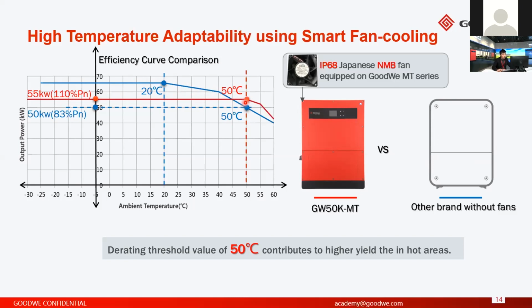But only if the temperature is more than 50 degrees, the inverter starts to decrease the AC output. But if you check this blue curve, the inverter starts derating from 20 degrees. So if you use this brand in Sri Lanka, you will lose a lot of power generation, okay, because of the temperature issue.